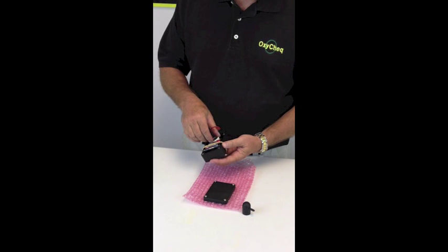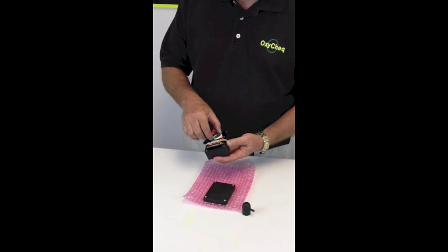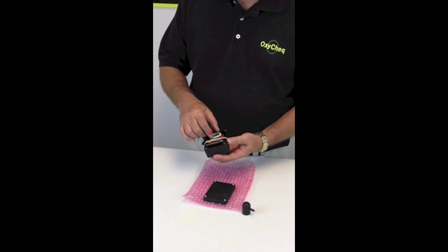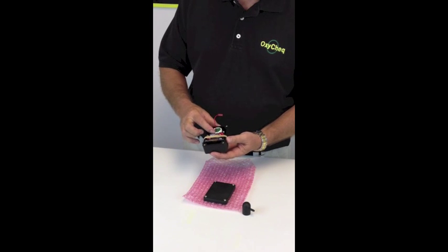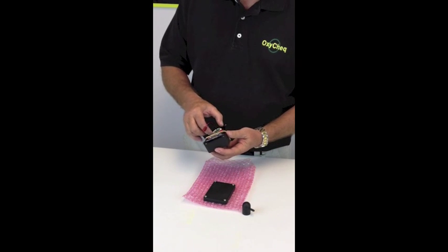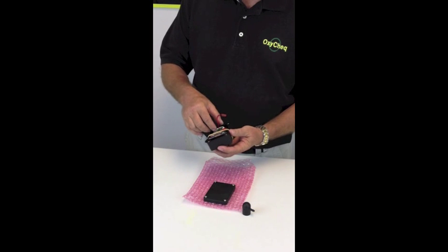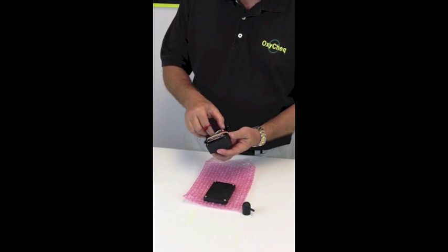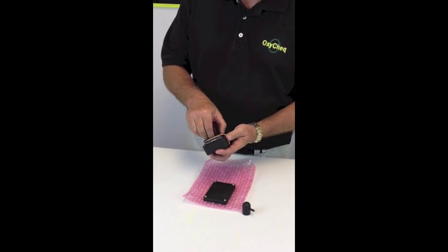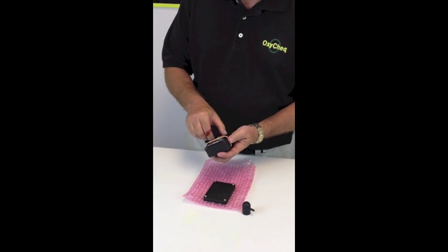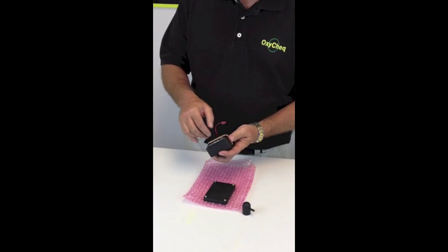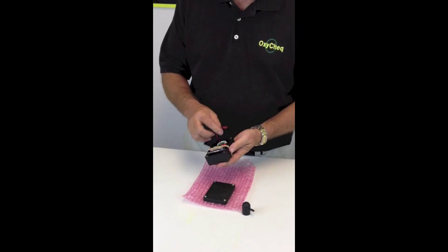We're going to screw this in clockwise, righty-tighty. Make sure that you don't have any resistance on the sensor itself. It should go in very smoothly, as you can see. If it's cross-threaded, you can cause damage to either the case or the sensor threads itself. So take your time with this. And it'll take several turns to get it in place.